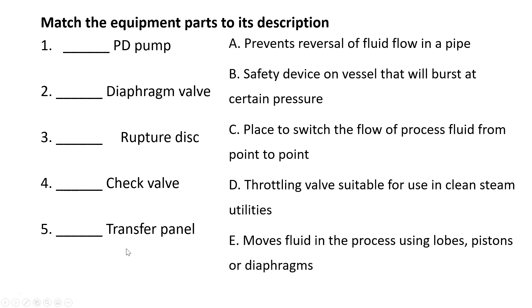We're going to start off with the matching section. PD pumps are E — they move fluids in the process using lobes, pistons, or diaphragms. Diaphragm valve is D, a throttling valve suitable for use in clean steam utilities. A rupture disc is B, a safety device on a vessel that will burst at a certain pressure. Check valves are A, they prevent the reversal of fluid flow in a pipe. And transfer panel is C, a place to switch the flow of process fluid from point to point.